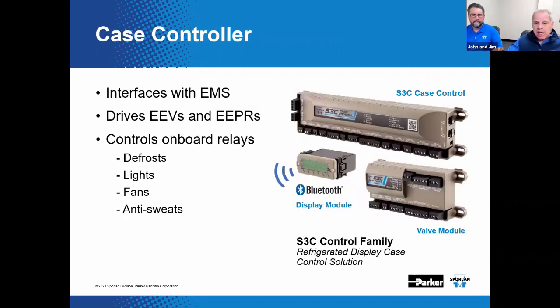We've already talked about some standalone devices. Here's an example of another type of control that can easily interface with that building EMS, and it can control many additional parameters. This is just an example. Now, this S3C case control is a device that can control defrost, lights, fans, anti-sweats, and interface with the EMS. And we have an online training module for this control with more of that type of thing on the way. And these case controls are typically in communication with the building system, which gives it a lot of flexibility if you are to do that.